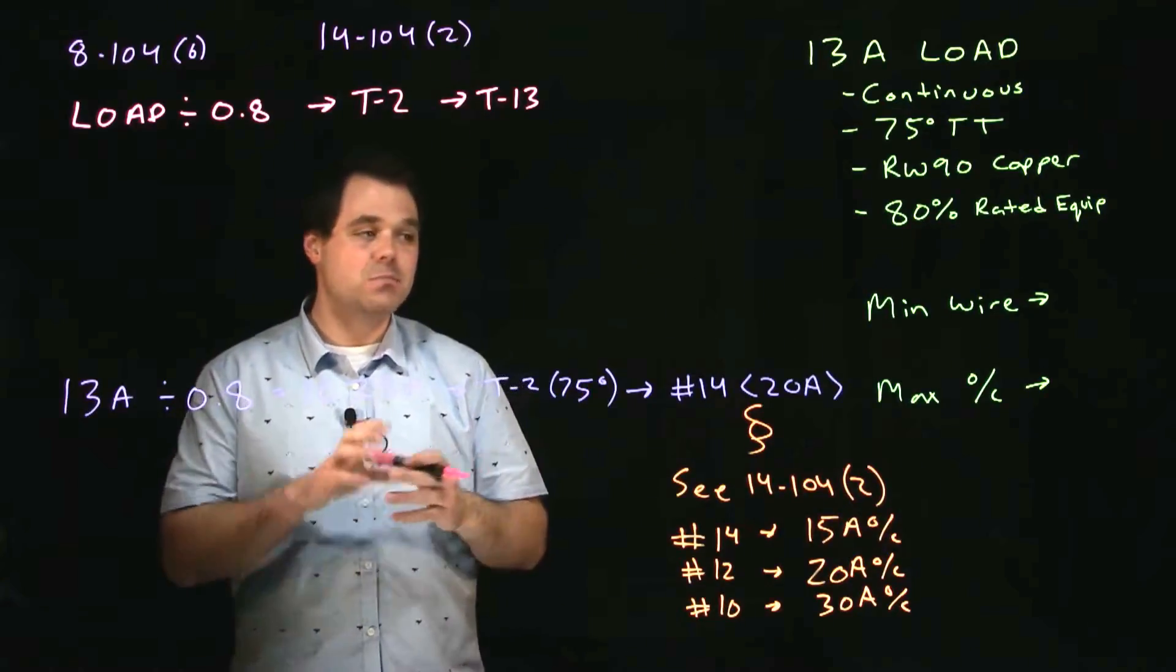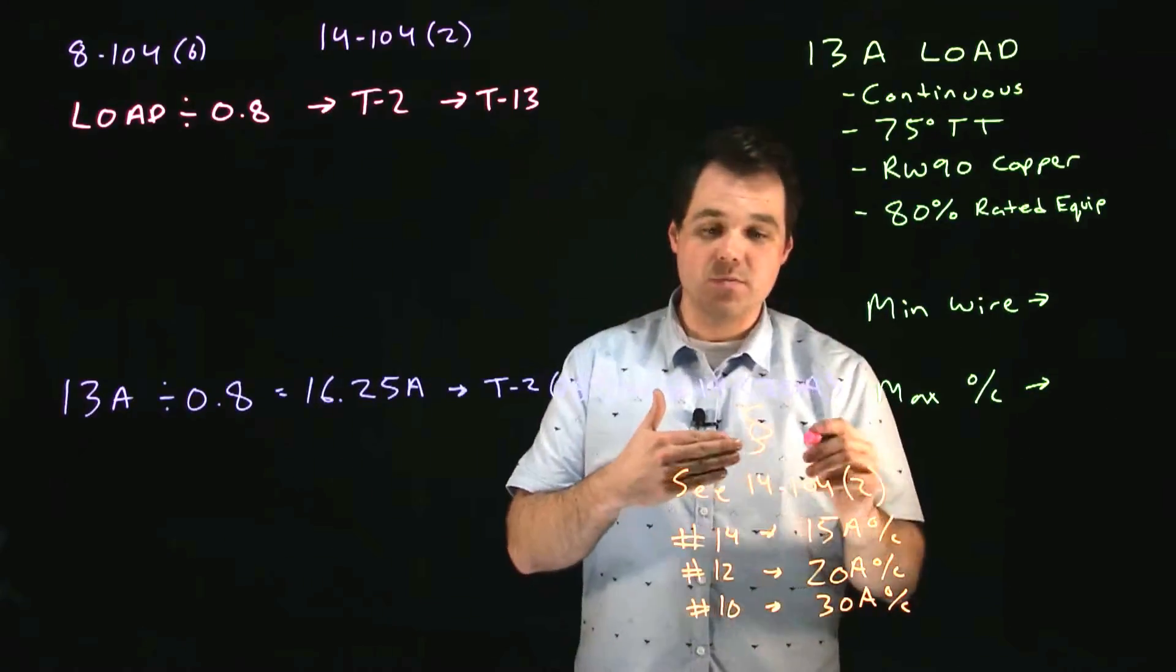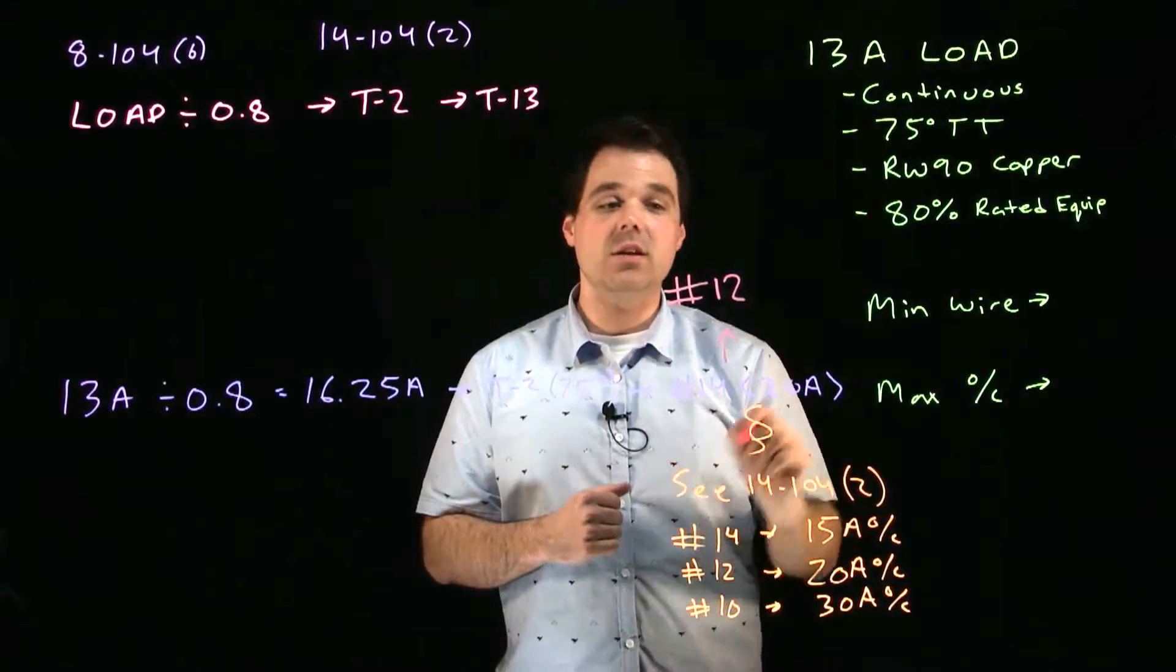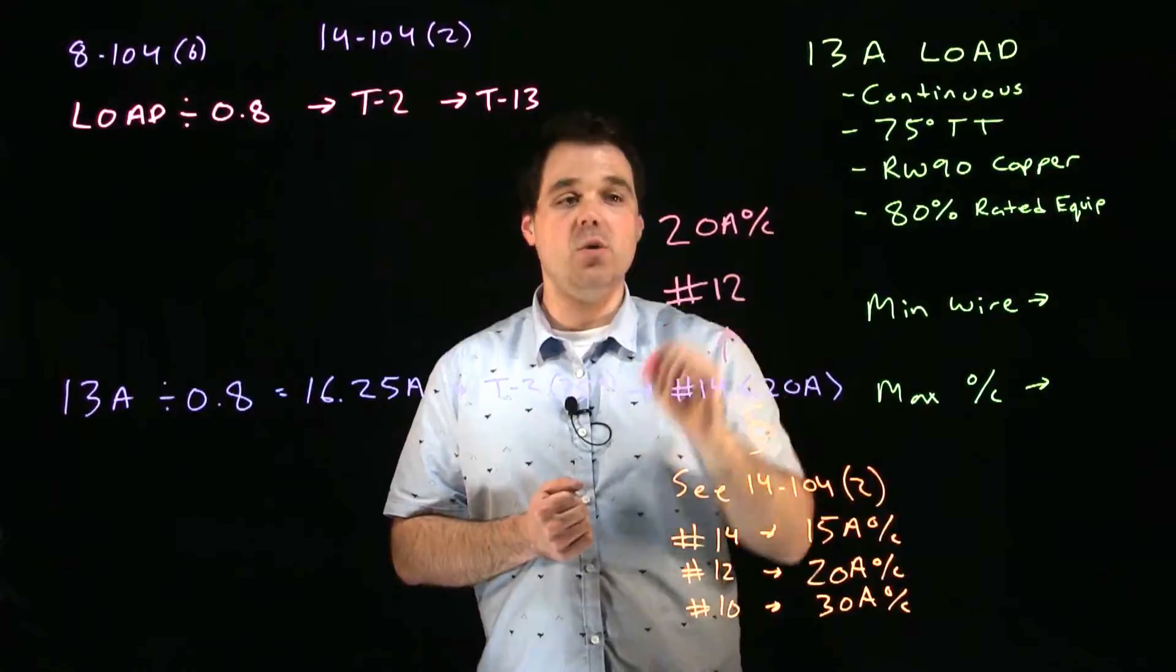So in this case because I need to upsize that breaker I am also upsizing my wire. Which means I have to upsize this to a number 12 gauge wire which is allowing me to use a 20 amp OC.